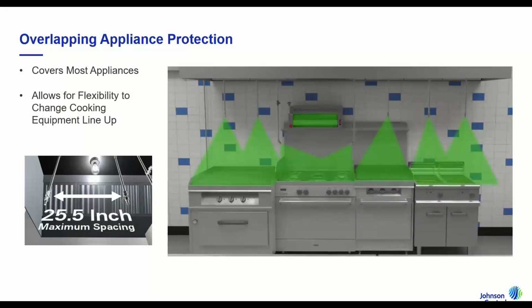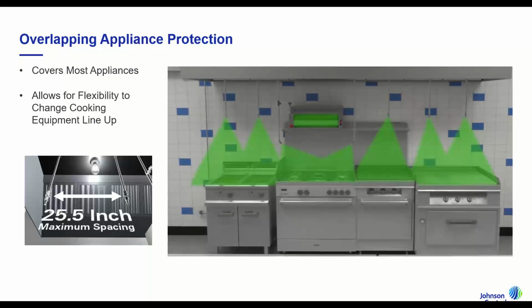The other option that we have is our overlapping coverage. And this essentially has nozzles spaced equally throughout the hood. And this allows you to move the appliances underneath that protected area. There are still limits and maximums of what can be covered under the overlapping scheme. But the value of it is if you have a change of a chef or a different appliance, whatever you need to switch in or out, as long as it falls within that criteria, they can be moved as much as needed and no changes are needed to the suppression system. So this is just a simulation of switching the fryers and the griddle from one side to the other. Appliance coverage did not change.